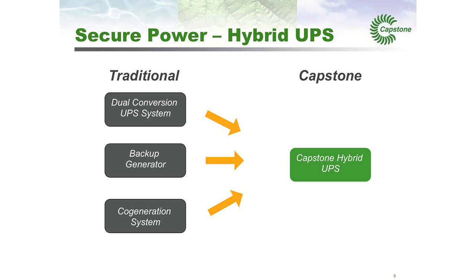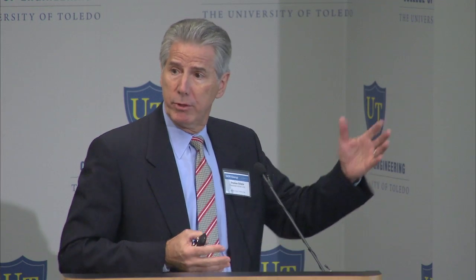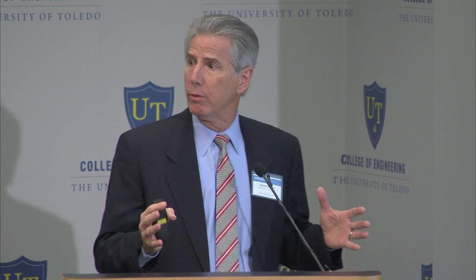What we realized is that the traditional way of protecting a system requires redundancy, because the utility grid isn't always going to be available, so you need backup. Traditionally that backup is a double conversion UPS system plus a backup generator. The UPS handles short outages, maybe 10, 15 minutes up to an hour depending on the battery bank, while a backup diesel generator handles longer outages.